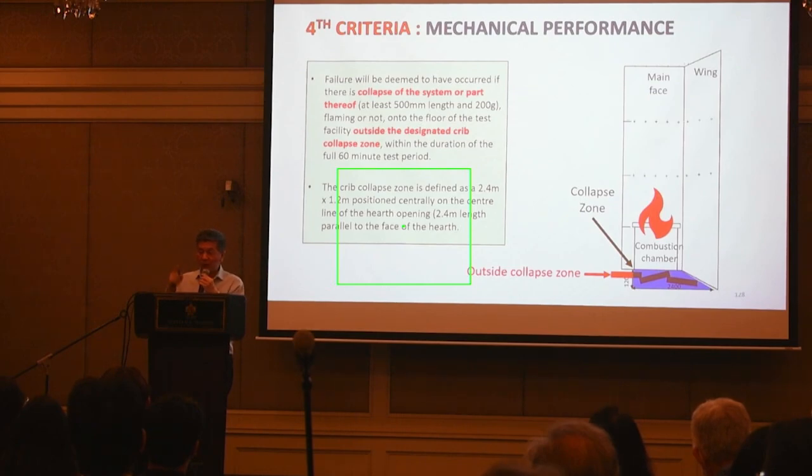Now that brings to point my first question. Why, with ACP, do you see a big hole? The reason is at level 1, temperature can go up to 900. So what's the melting point of aluminum? Anyone knows? 650 or 660 degrees Celsius. That's the melting point of aluminum. So at level 1, when it's 900, that's why you can see it's really gone. Evaporated, melted, whatever, right? So when it melts, maybe there are pools of fire.